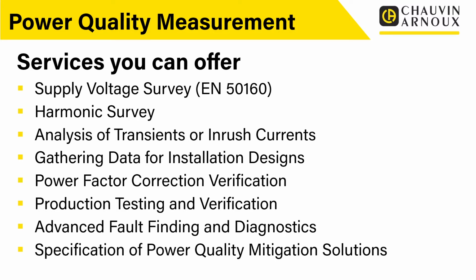The final bit here is specification of power quality mitigation solutions. So if you're going to recommend to your customer that they fit power factor correction, you need to know what you're trying to correct - what is it now, what do you want it to be, what are the characteristics - so you can either order the correct mitigation solutions, or work with a third party provider as a consultant. You provide them with all the data, they provide you with the correct solution, you fit it, and then you can go through and do your verification, check it's there and working.